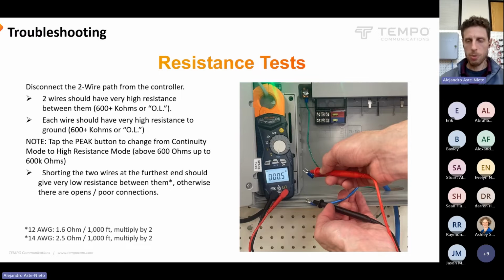A test we can do just to see if the wires are any good. We can short our 2 wires in our 2-wire path at the very far end, and we should now have a very low resistance between the 2 wires. This is just my tiny little test rig, so it's a very, very low amount. But out there in the real world, you'll have longer runs of cable, so you'll see higher numbers.